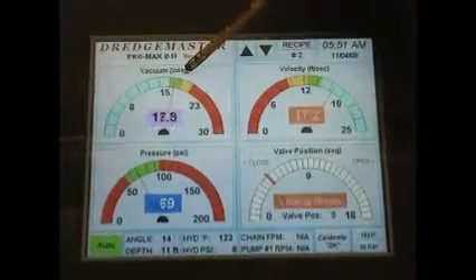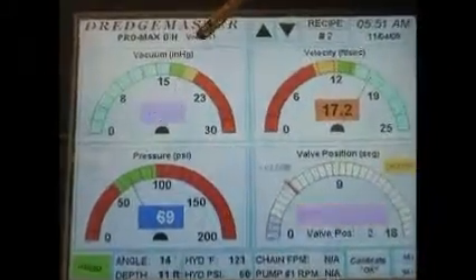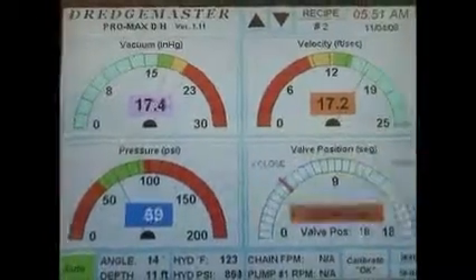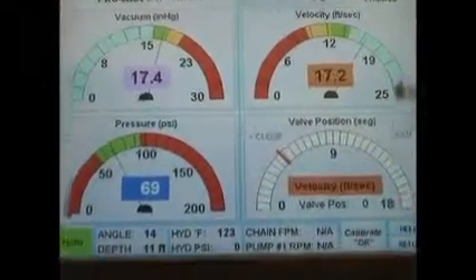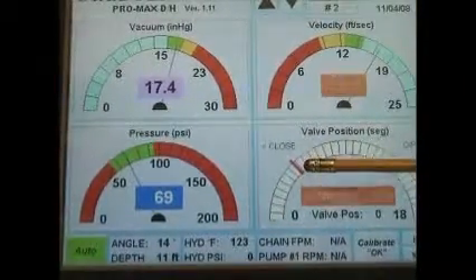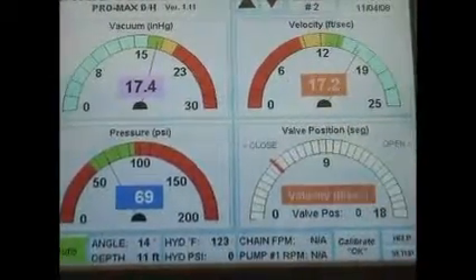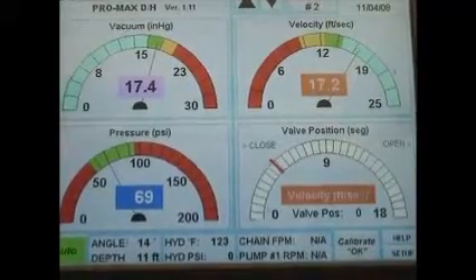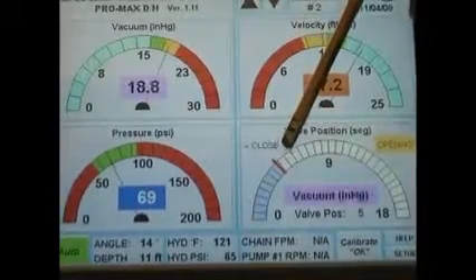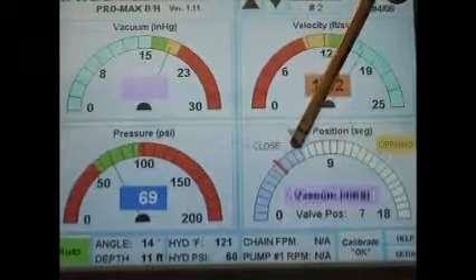So as our vacuum starts to increase, once we get into the yellow zone, you can see the valve is now opening a lot more rapidly. Once the valve has calibrated itself, we'll demonstrate how the valve opens more rapidly from fully closed to our 2-speed set point, and from our 2-speed set point on, it will go in a slower mode. So our valve opens up twice as fast. Now once it gets past our 2-speed, it again goes at the rate it normally would.